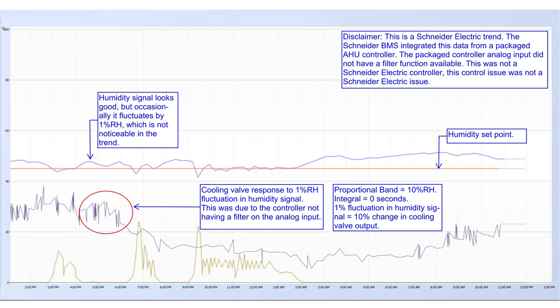He's like, what's a filter? I don't know what you're talking about. No one told me that. And I don't think all BMS companies, maybe they don't have a filter. It's a time-based filter. What it does is it looks at the process variable and then over like 1 minute, or however you adjust it, it filters it so that it's more stable. You don't get the peaks and the troughs of the signal.